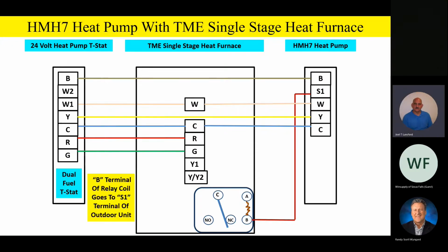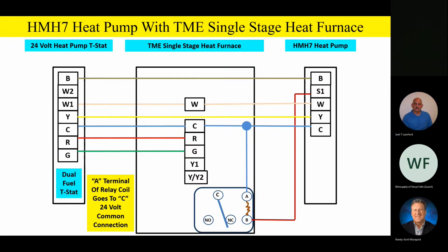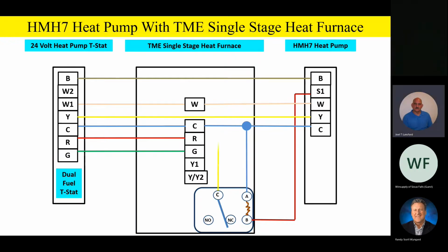One side of our relay coil is going to go to S1. The other side of the relay coil is going to go to common terminal. And then the common terminal for the switching contacts is going to go up and hit yellow again, so that anytime we have a compressor call, we're going to energize that common terminal on the switching contacts. Now watch this, the normally closed contact on the relay is going to go to Y/Y2 for high-speed cooling airflow. And the normally open contact will go up and hit Y1 for low stage cooling.